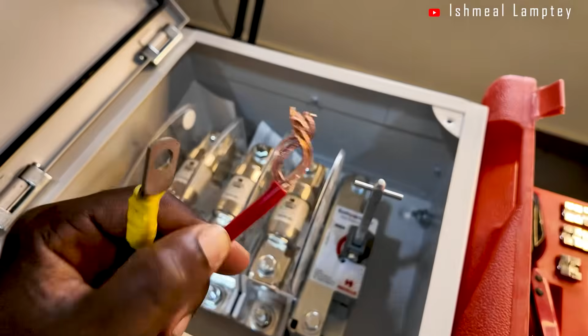So if you open your TPN and you've seen that the electrician has done this, please try and get him back to come and correct it, because this is one of the things that causes fires. Because in this case, you have loose contact, because look at how this is done. There's no way this is going to be as tight as this. In this case, you have a very loose contact over here.